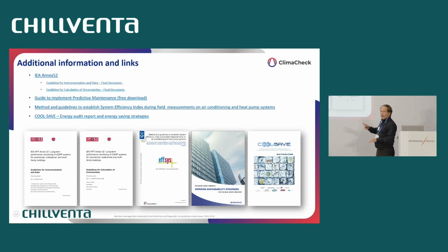So there's a lot of documentation. In this one, there's a description of definitions for System Efficiency Index and so on. Annex 52 is actually for ground source heat pumps, chillers. But everything in this, I would say, will be generally applicable for any refrigeration, air conditioning, heat pump process. So very good advice on how you monitor long term. We try to apply everything there. And predictive maintenance, we try to push that this is the future. CoolSave is a report on industrial refrigeration improvement possibilities.